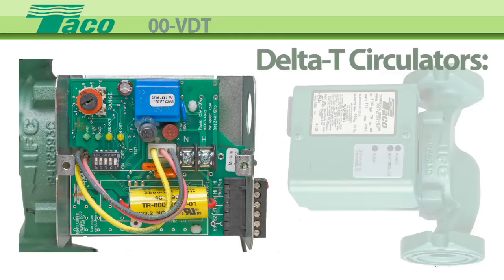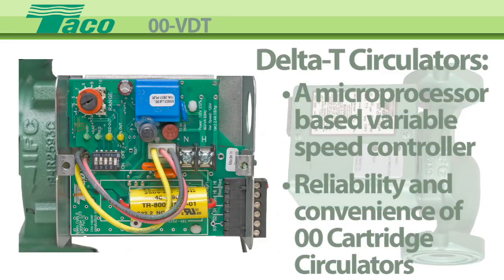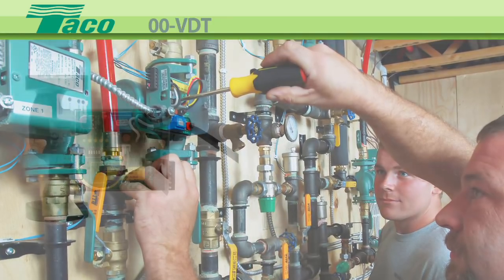Taco variable speed delta T circulators combine a microprocessor-based variable speed differential controller with the reliability and convenience of our double O cartridge circulators. Simply dial in the design delta T from 5 to 50 degrees and sit back.